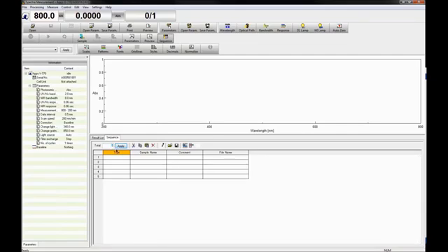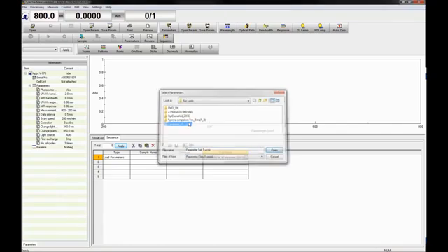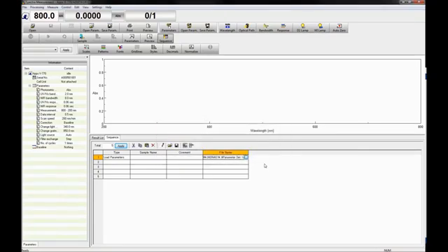The type column specifies a baseline or sample measurement, or a new parameter file can be loaded for subsequent sample measurements. Select the cell under type and then right-click to choose the measurement type. If load parameters is selected, the parameter file name has to be specified in the file name column. Click the corresponding cell in the file name column and click on the button to the right and then locate the parameter file. Any data processing or sequence settings previously specified in the parameter file will be ignored.